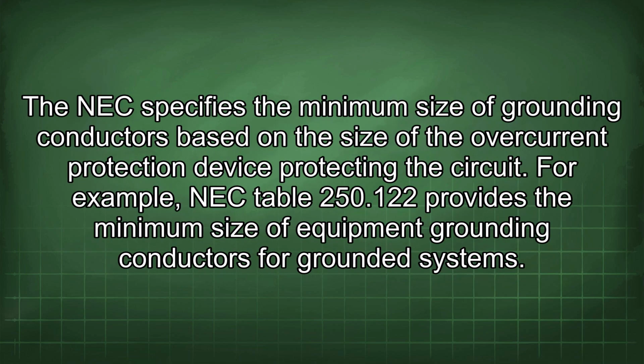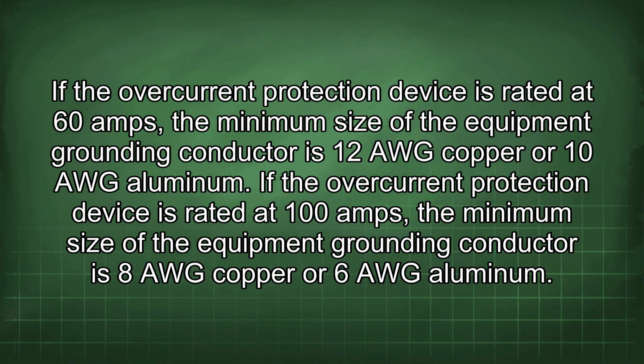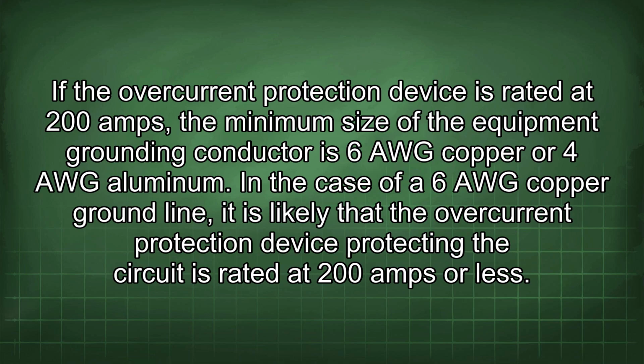making it a good choice for grounding conductors. The NEC specifies the minimum size of grounding conductors based on the size of the overcurrent protection device protecting the circuit. For example, NEC Table 250.122 provides the minimum size of equipment grounding conductors for grounded systems. If the overcurrent protection device is rated at 60 amps, the minimum size of the equipment grounding conductor is 12 AWG copper or 10 AWG aluminum. If it is rated at 100 amps, the minimum size is 8 AWG copper or 6 AWG aluminum. If it is rated at 200 amps, the minimum size is 6 AWG copper or 4 AWG aluminum.